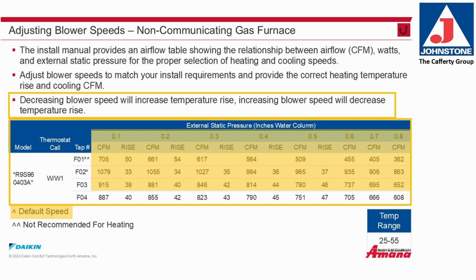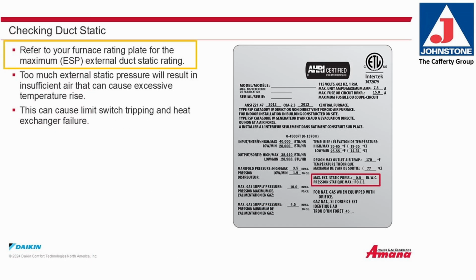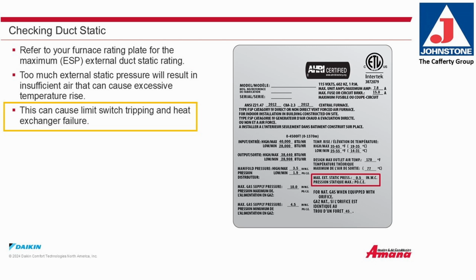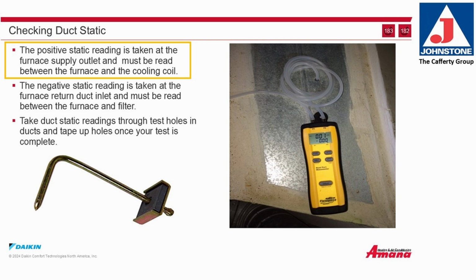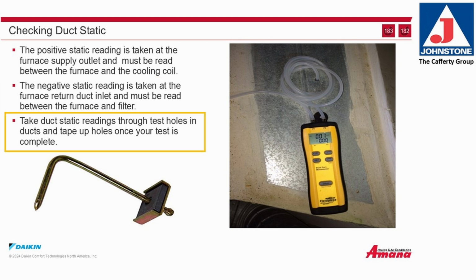Checking duct static. Refer to the furnace's rating plate for the maximum ESP, or external duct static rating. Too much external static pressure can result in insufficient airflow that can cause excessive temperature rise. This can cause limit switch tripping and heat exchanger failure. The positive static reading is taken at the furnace supply outlet and must be read between the furnace and the cooling coil. The furnace negative static reading is taken at the furnace return duct inlet and must be read between the furnace and the air filter. Take duct static readings through test holes in the ducts and tape up the holes once the test is complete.